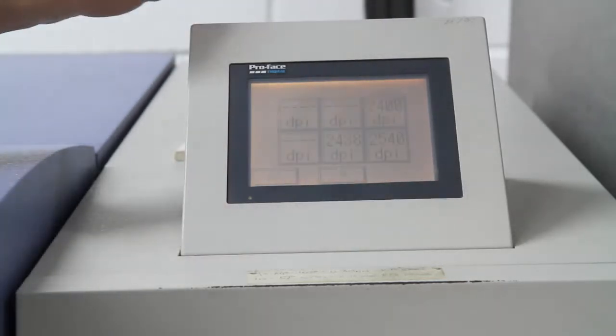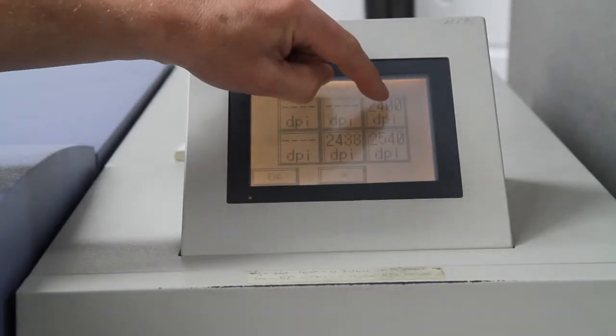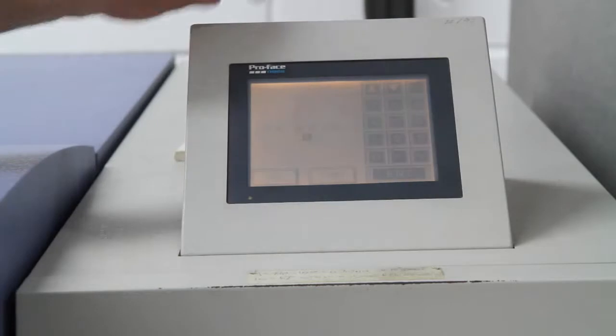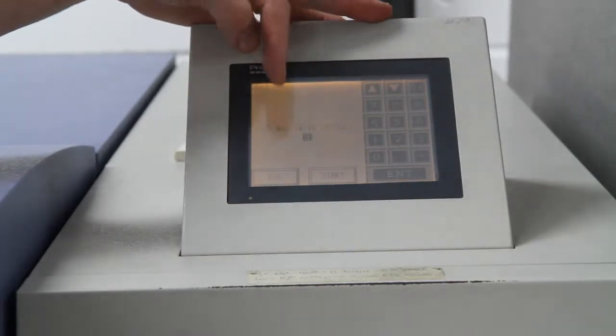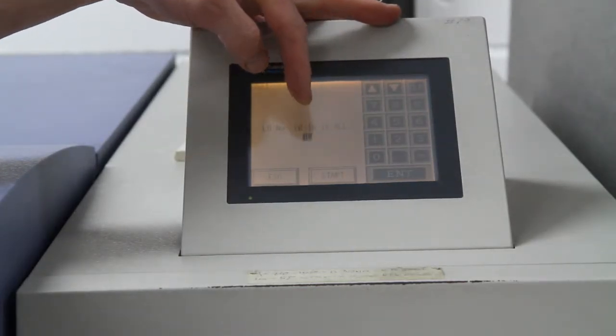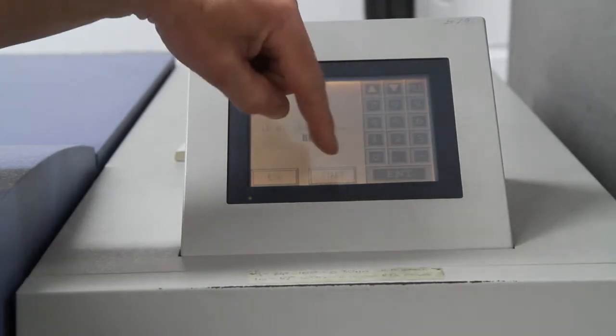That's the 2400, that's right. And we want all your laser diodes, which is 16. And we press start. That will go through and do a laser calibration. So just remember, every time you change plates between neg and pos, to calibrate. It'll still work, it's just more of a safeguard.